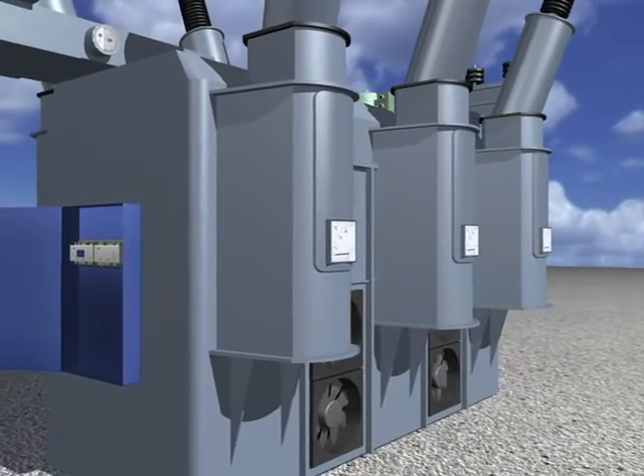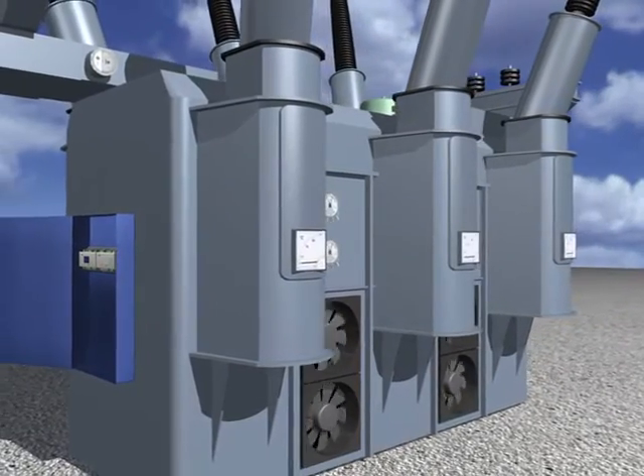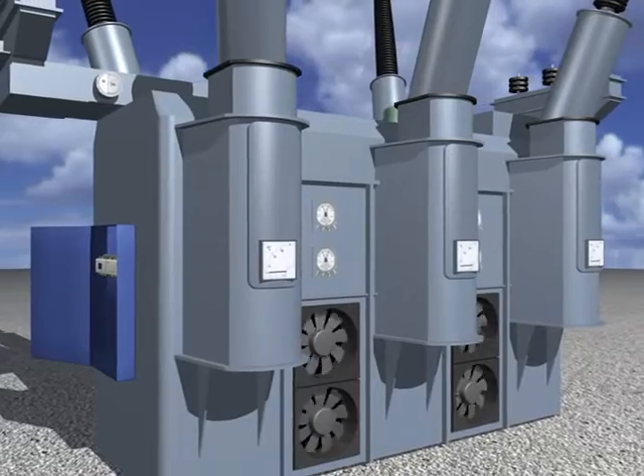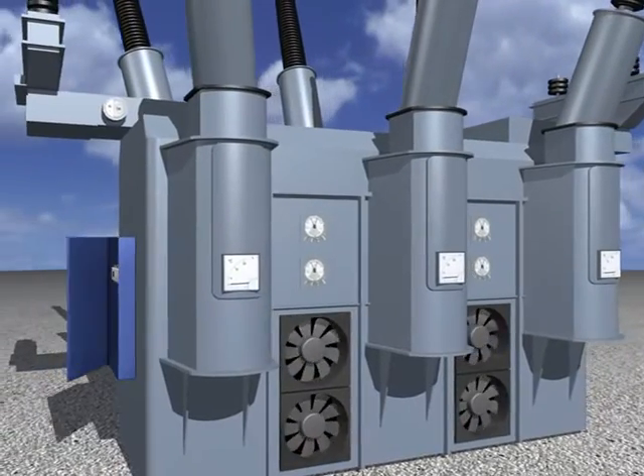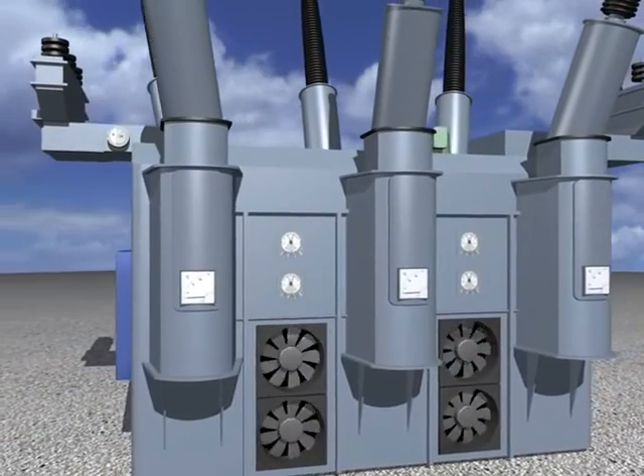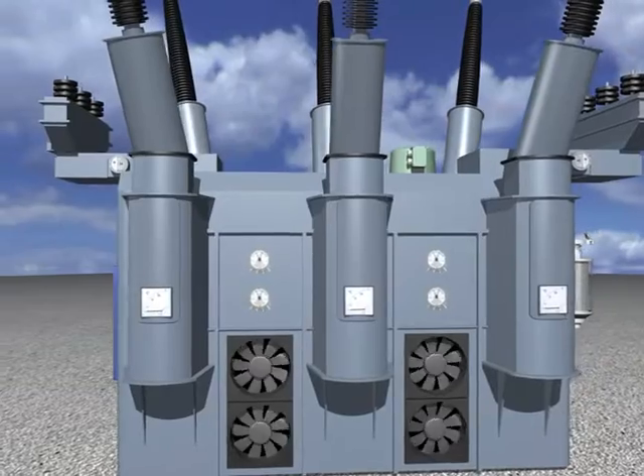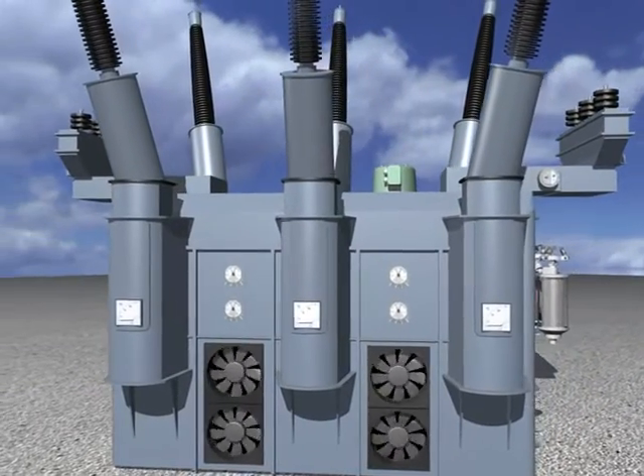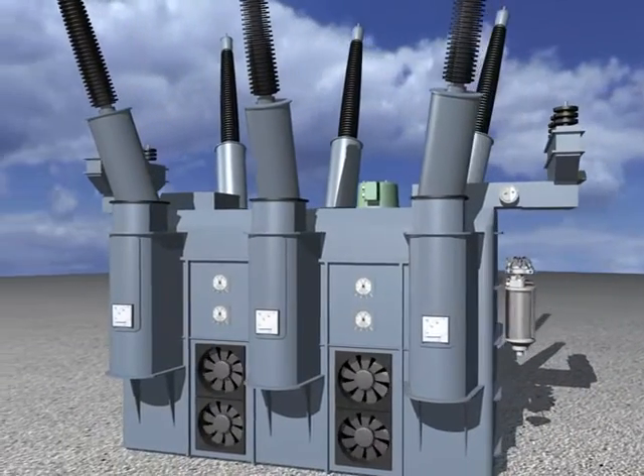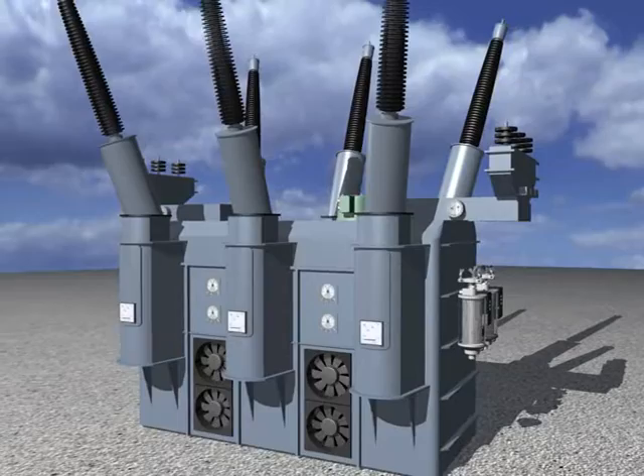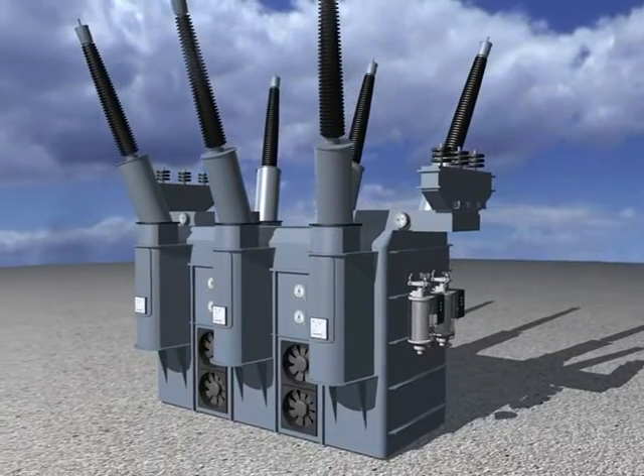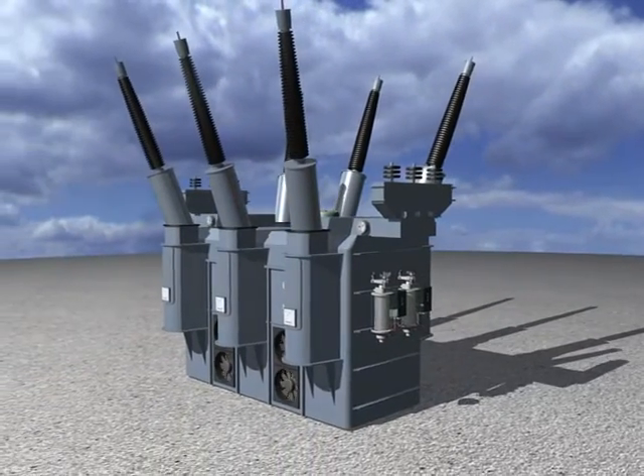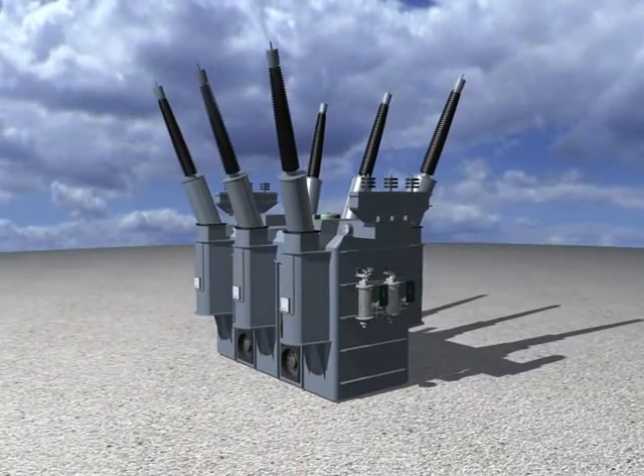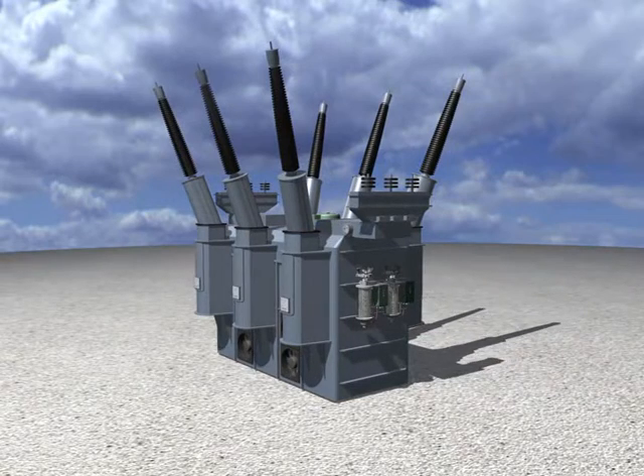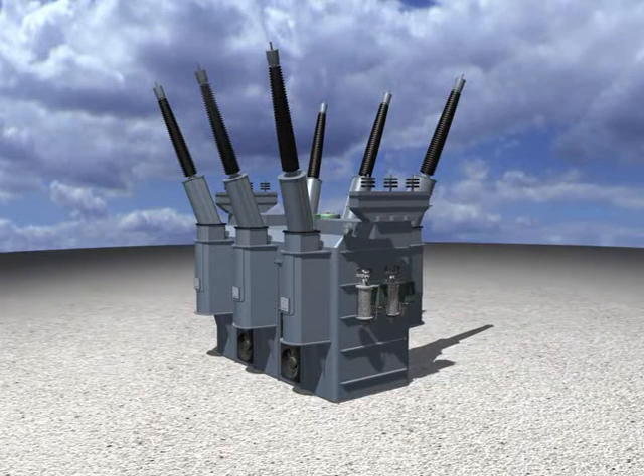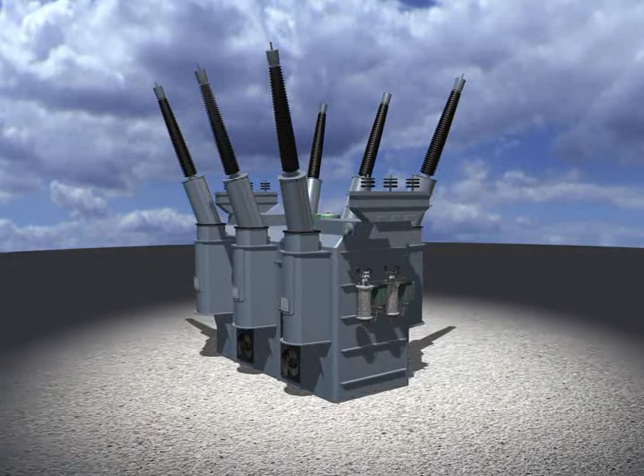Such transformers require precise measurement of the winding temperature to ensure that overheating does not damage the insulation of the transformer. An evaluation of the maximum economic efficiency which can be achieved during operation depends on accurate monitoring and realistic operational and maintenance strategies. Since power providers are also forced to increase utilization of their systems while employing fewer personnel, a change to these new systems is vital to survival.